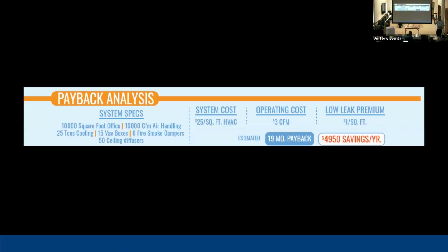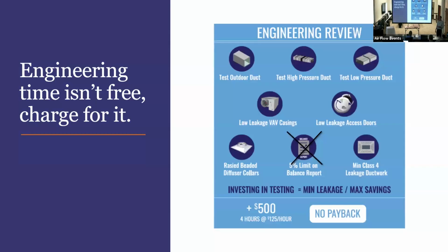I just did a ballpark estimate a couple of years ago. If it was $3 a CFM, which is really low, and if your system cost was $25, which is probably too cheap, if you paid a premium for that system to make it low leak, and you paid $1, so we went from 25 bucks to 26 bucks, what would the payback be? And looking at a medium-sized office building, like our office could be something like this.